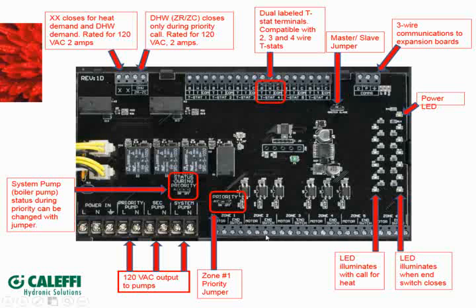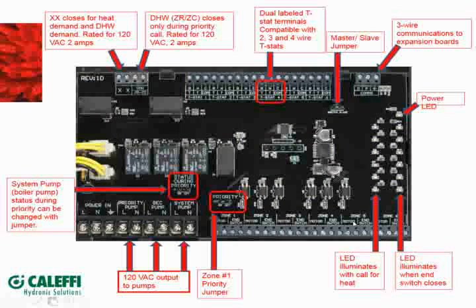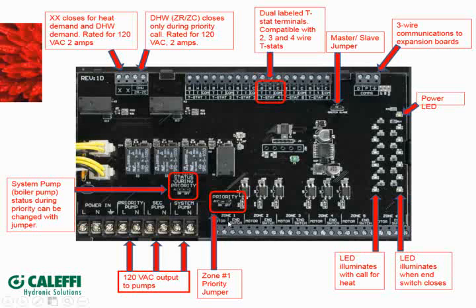Here's our output for our zone valves. We label it as motor and end switch, which matches what we have on our Z151 actuator, the terminal block actuator. But if you're using a Z111, our black leads go to the motor and our red leads go to the end switch. And like I mentioned, zone 1 is always our priority. So whether it's a 3-zone, 4-zone, or 6-zone, zone 1 is always priority. That way it's always consistent.